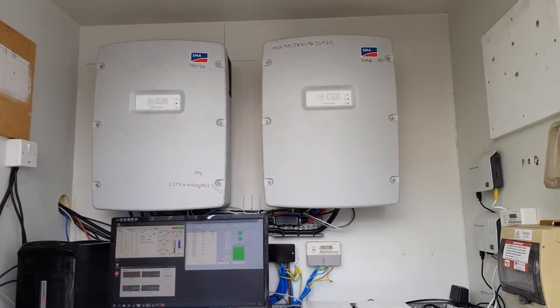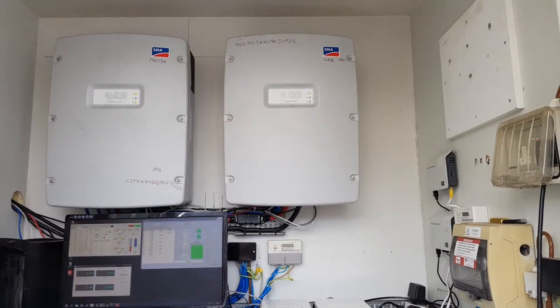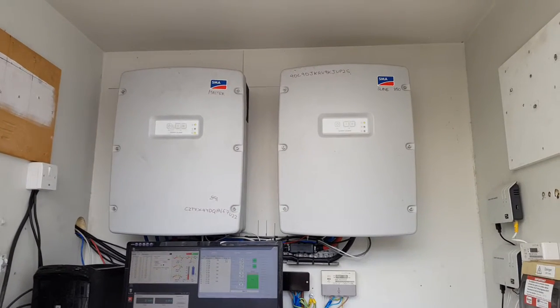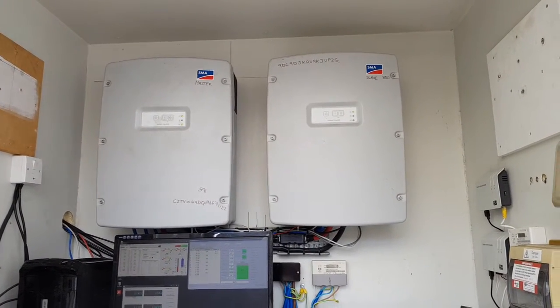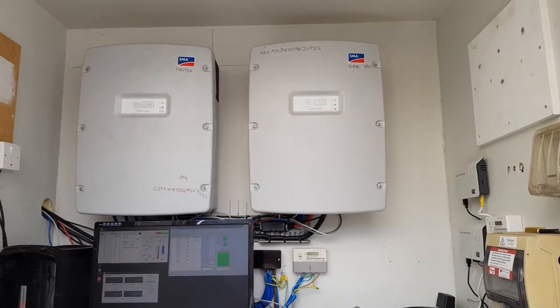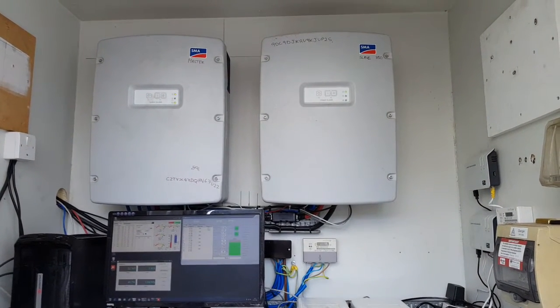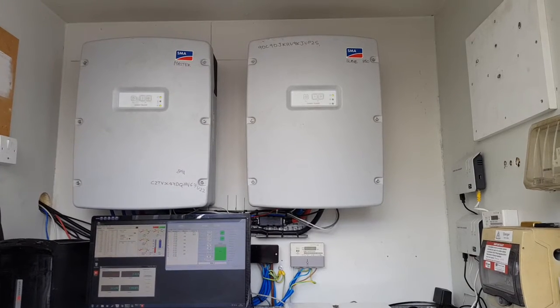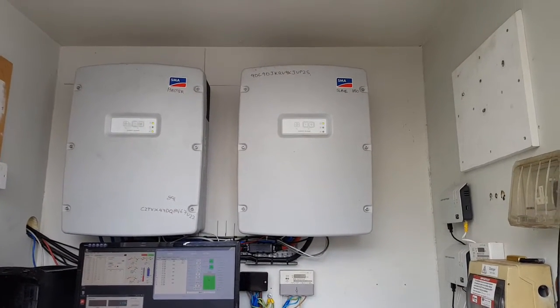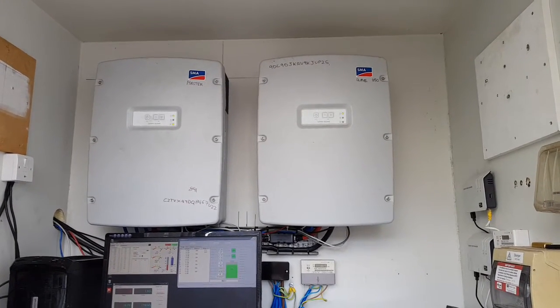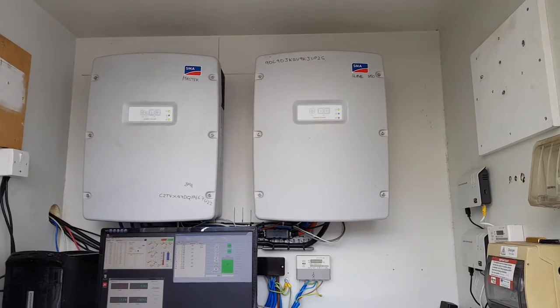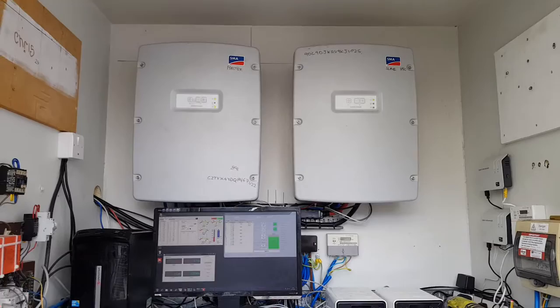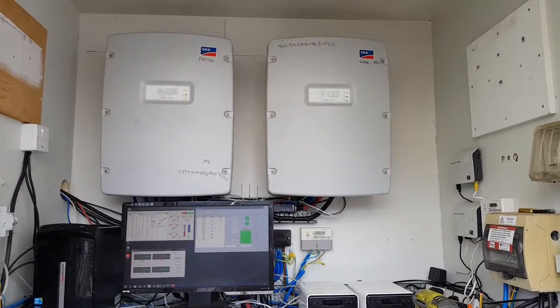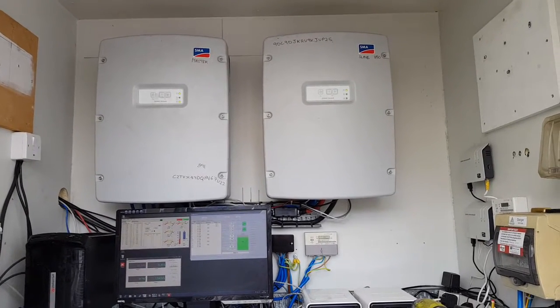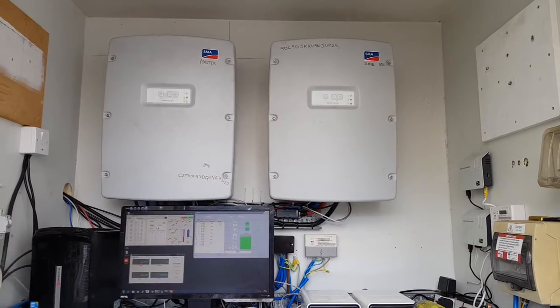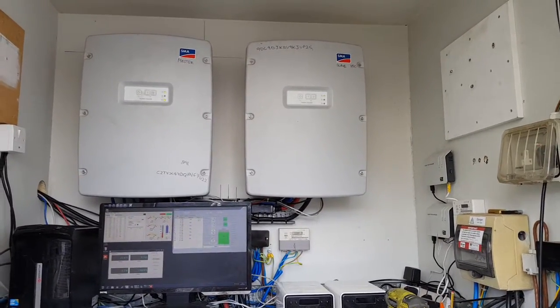Everybody wants to know right at the beginning about inverters. So what you see there are the off-grid inverters, Sunny Islands 8, wired in parallel. They do everything to do with the batteries, converting DC from the batteries into AC to run the house. They're also charge controllers as well, so both charge controllers and inverters, but they are not linked directly to the PV solar panels. They're literally just to do DC voltage to AC, and AC voltage to DC for charging, so charge and discharge. That's those two.